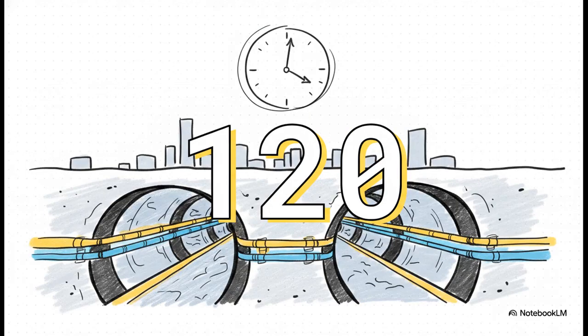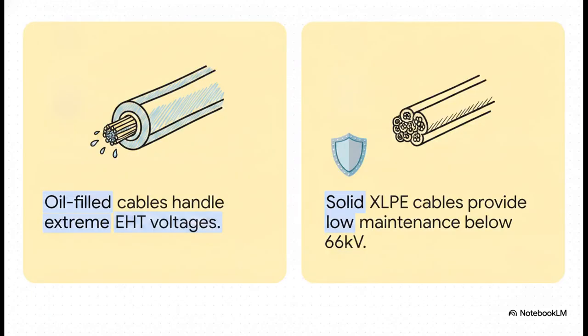And honestly, the most fascinating part of this underground marvel is that it's designed with an unprecedented 120-year lifespan. By placing it so deep and building it so robustly, they've ensured this massive asset won't need to be dug up and disrupted for over a century. That's a serious long-term play. Now, depending on which rung of the voltage ladder you're on, the actual cable technology running through those tunnels shifts dramatically. For the extra high voltages, those 400 and 230 kilovolt lines, they use oil-filled, paper-insulated cables. This gives them superior insulation performance at those extreme voltages. But drop down to 66 kilovolts and below, and the network shifts over to solid dielectric XLPE cables.